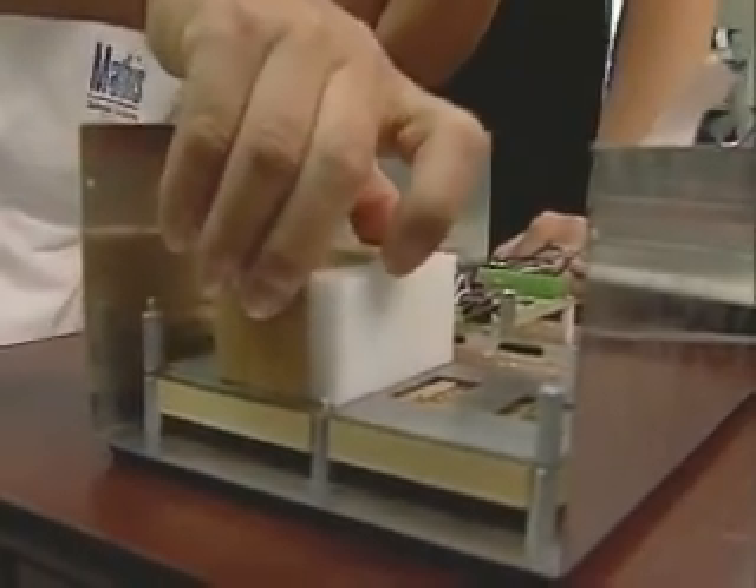Thermal conductivity testing before used to be conducted on samples that were one foot square and one inch thick. They were put into an instrument similar to a VCR, and you had to wait for roughly an hour to get the measurement. With our sensors, they operate more like a stethoscope. A sample is put in contact with our sensor, and in roughly five seconds you have the answer for the thermal conductivity or the thermal effusivity. We have heating elements that supply the heat source into the material being tested and also monitor the temperature that results from that. This is the heart and soul — it sits inside the overall sensor, and this is what the customer interacts with. This sensor is placed on top of the materials under evaluation, it supplies the heat, and it detects the heat flow. In about five seconds you have a measurement of the thermal conductivity and thermal effusivity — worlds away from the half hour to hour that it used to take before.